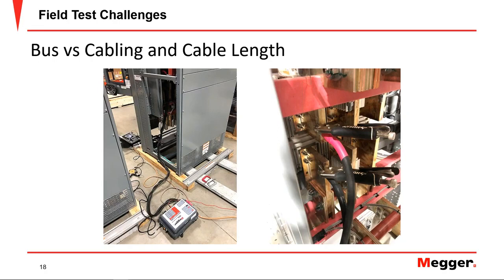We mentioned that it's important in this case to look at the recommendations from the standards. In this case, NEMA AB4 tells us that for these types of tests, the connections to each pole of the breaker should be made by copper conductors no less than 4 feet in length, right? And they even give us recommendations for the size. They have a table that, depending on the rated current for the breaker, recommends a size for the cables or conductors to be used. So that's a good table to look at to determine the right size or gauge that I need for my test.